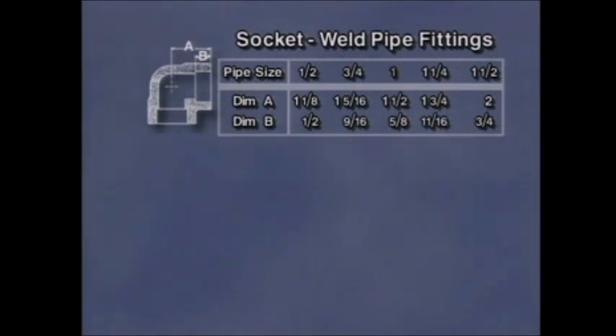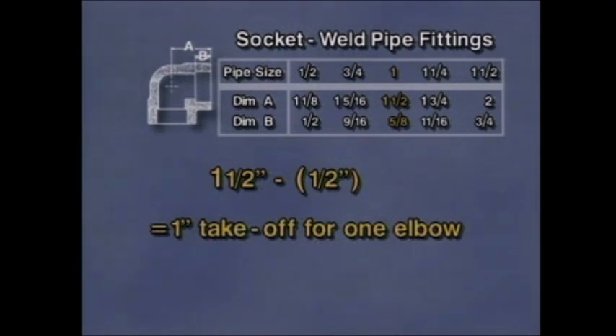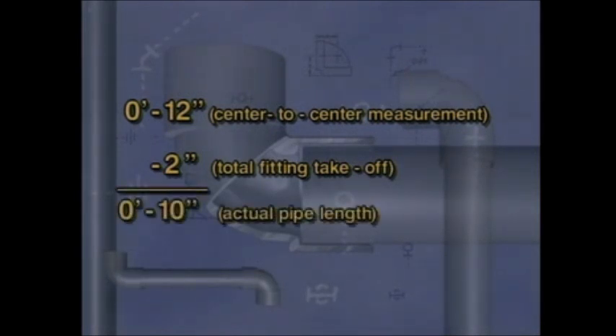For example, a one-inch socket weld 90-degree elbow is one and a half inches from end to center, dimension A. The make-up, dimension B, is five-eighths of an inch. But with socket welds, the pipe must be backed out one-eighth of an inch to allow for heat expansion, so the true make-up is four-eighths, or half an inch. Subtract the half-inch make-up from one and one-half inches, and the takeoff for one fitting is one inch. Since there are two fittings, multiply that by two, and the total takeoff is two inches. Subtract two inches from the center-to-center measurement and you get the actual length of pipe required — in this case, ten inches.